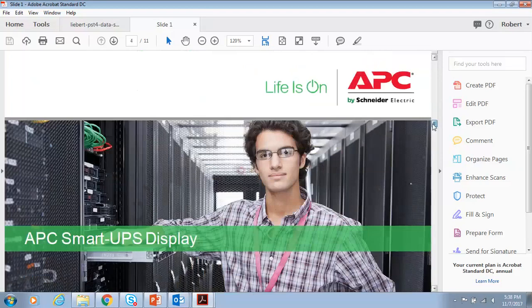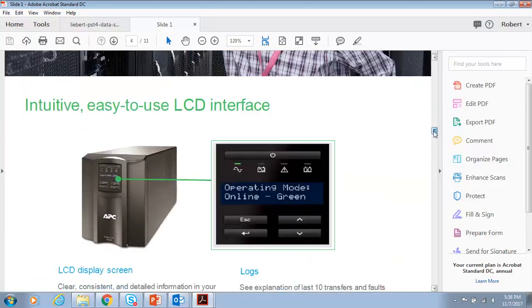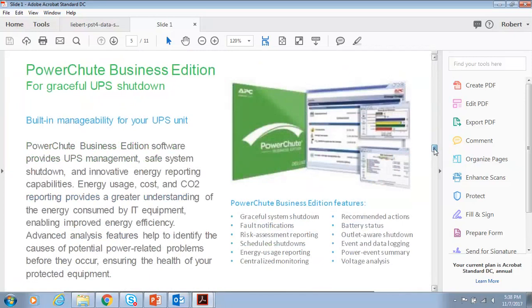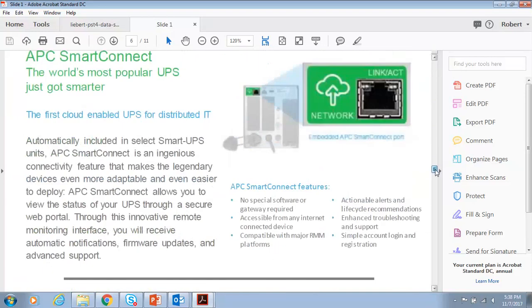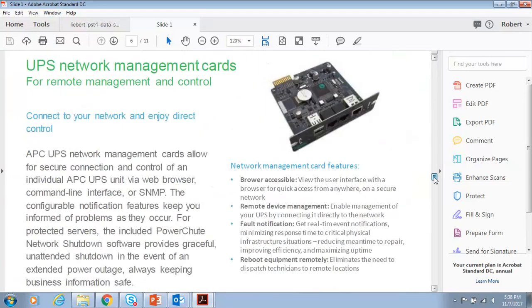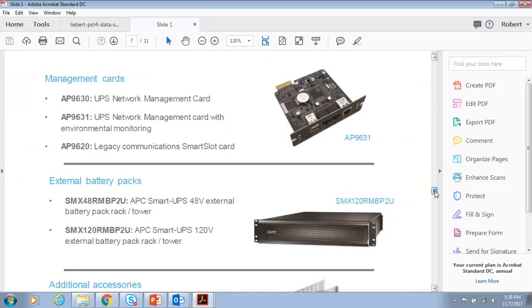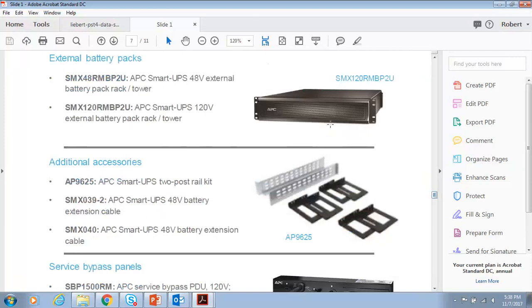As you move down here, you'll see things like user displays on the units, and software that, via the network connection and a network card in the unit, allows you to gracefully shut down and control which outlets go off at any given time. The network cards are different types of accessories; there are different network cards from both APC and Vertiv. And then the extended battery packs, which again are just rack-mounted chassis that have the extended batteries.